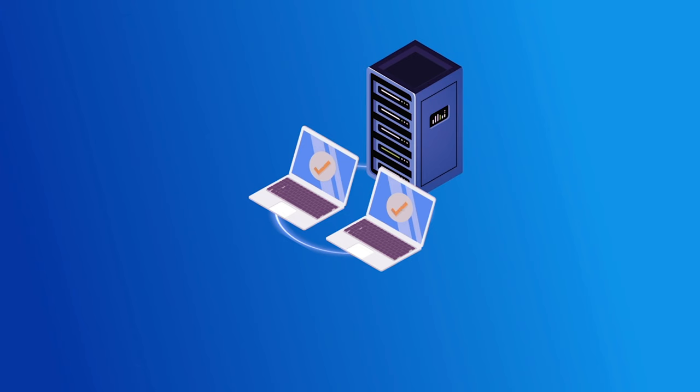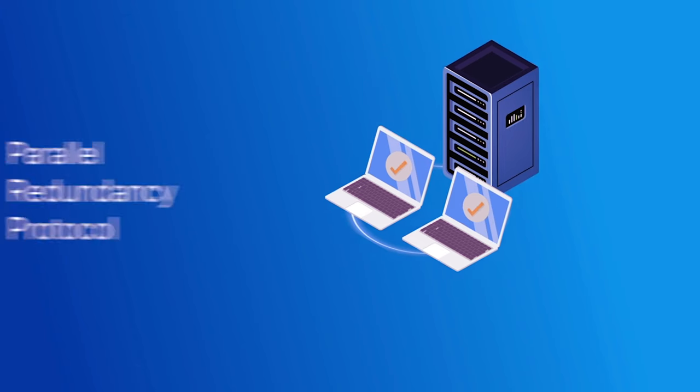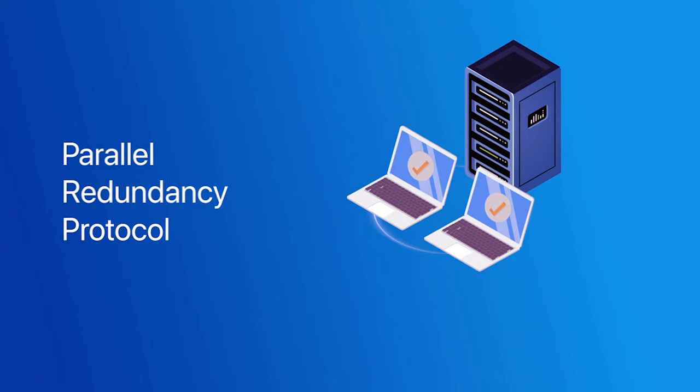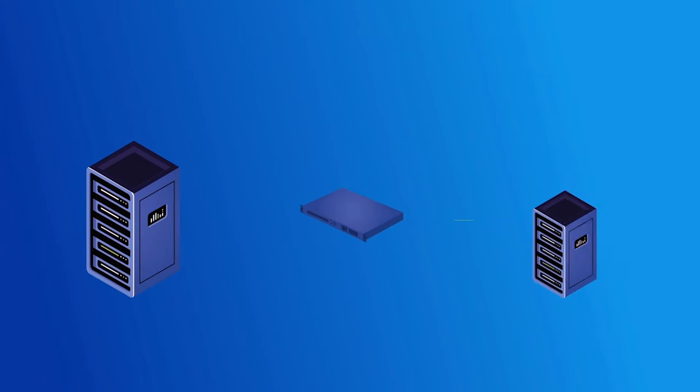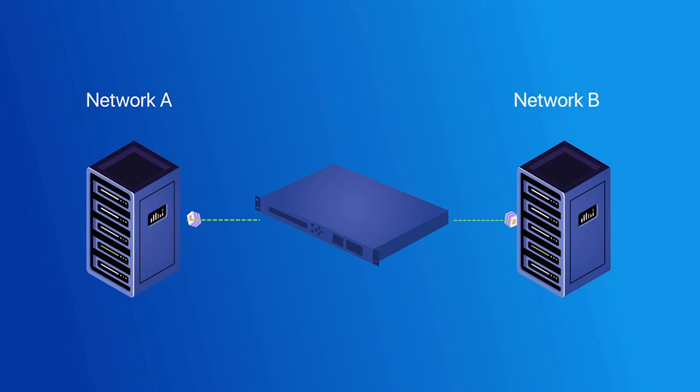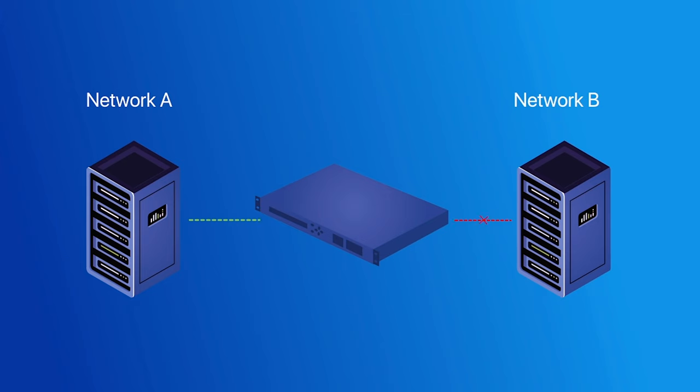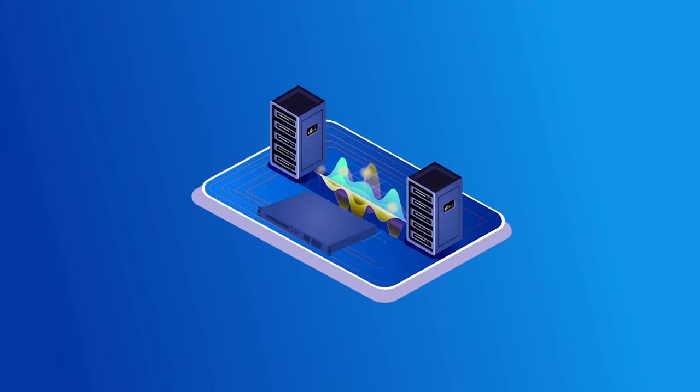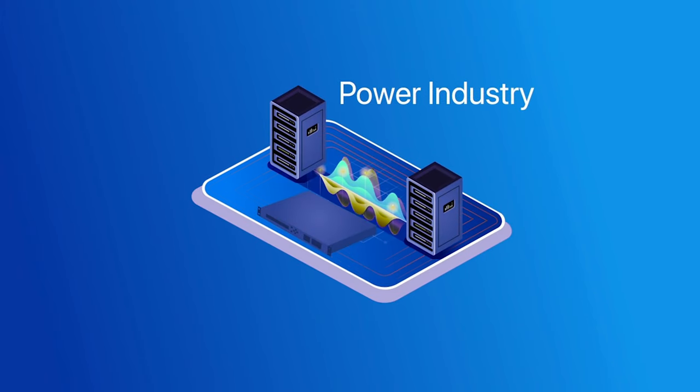PRP, or Parallel Redundancy Protocol, is one powerful solution for providing seamless network redundancy. With a PRP network, every device has two networks it can use to communicate with any other device. The same message is sent over each of the two networks, and when it gets to its destination, the first message to arrive is processed while the duplicate is discarded. Network redundancy is critical to the power industry.